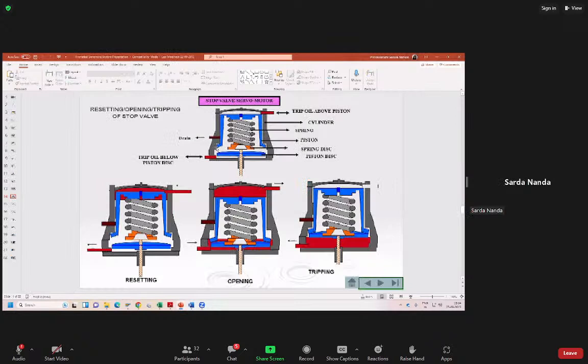See, you see this end of the piston, no? Right at this point, and the bottom plate, there should be a line contact. But there was a 20 mm piece that was chipped out of it, due to which there was no contact; that entire area had no contact. So that trip oil was getting drained through that area, into the drain port. And when we replaced the servo motor, it was fine. It worked fine.